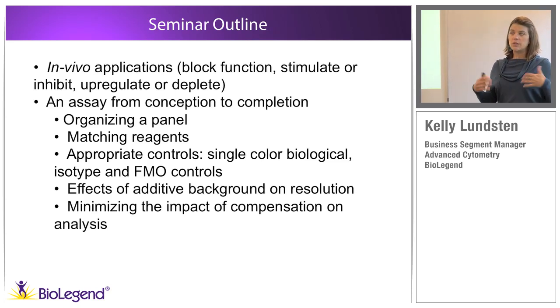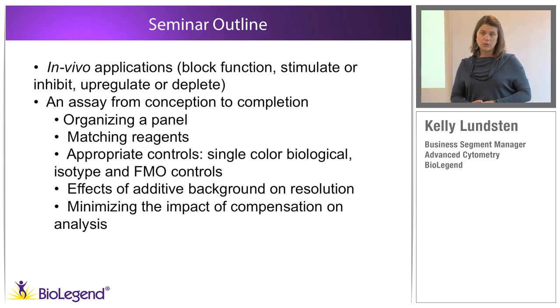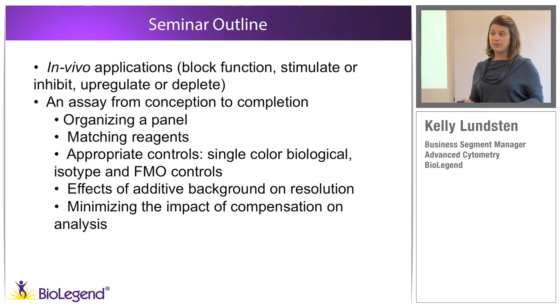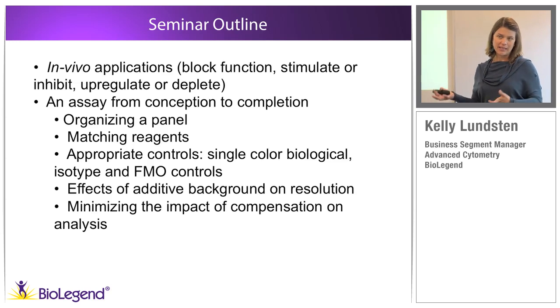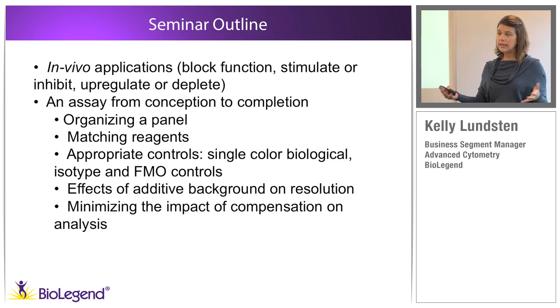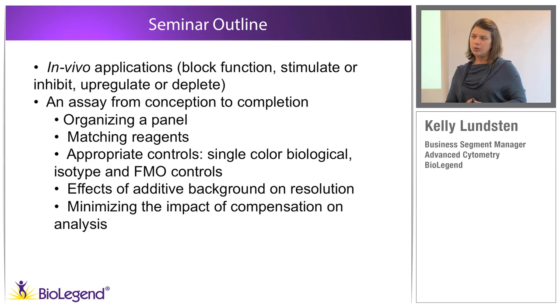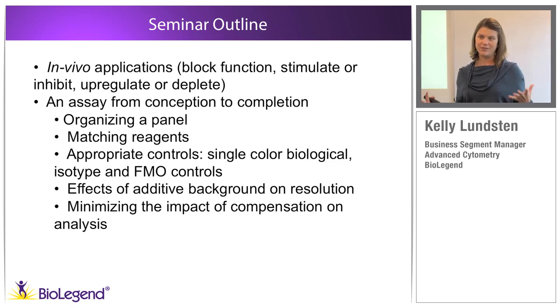We'll talk a little about isotype controls, mostly in the context of fluorescence minus one controls, and the additive effects of background on resolution. This assay will show a 15-color immunophenotyping example. When you're forced to use fluorophores like PE-CF594 or PE-Cy5 — nestled in a space where many overlapping spectra are populating — that can have a big impact on the spread of the MFI negative. We'll discuss photon counting error, a digital distribution of error from our inability to appropriately count a single photon.